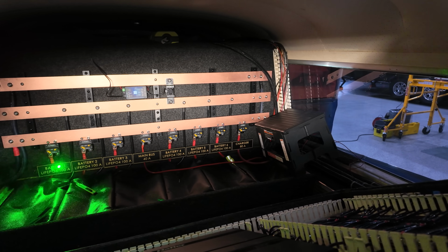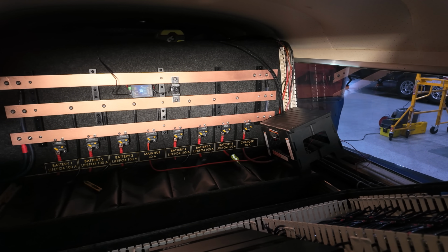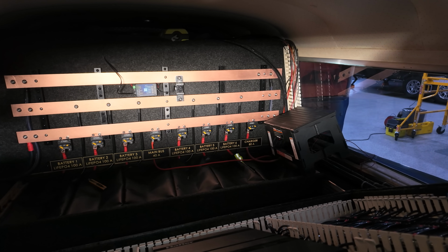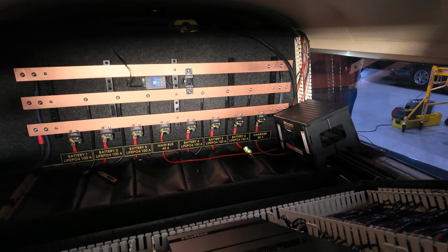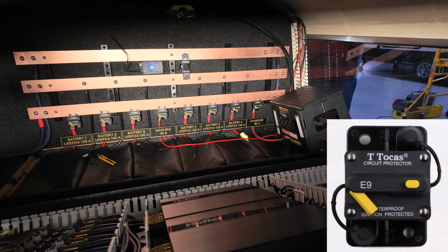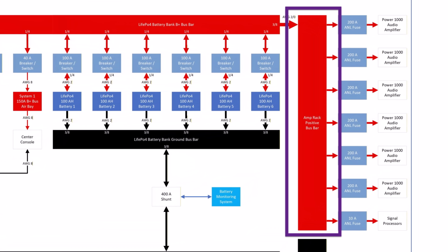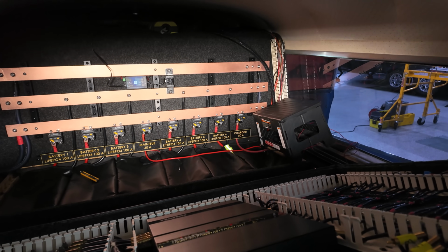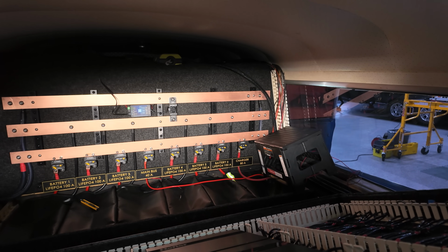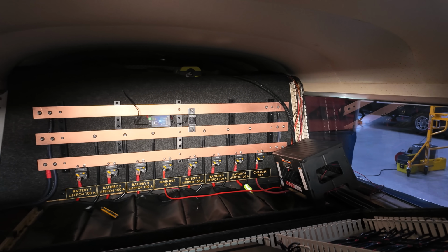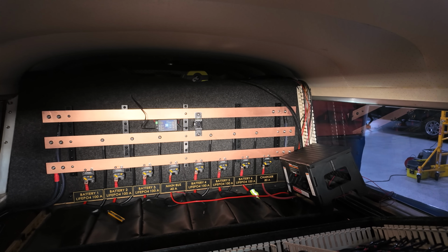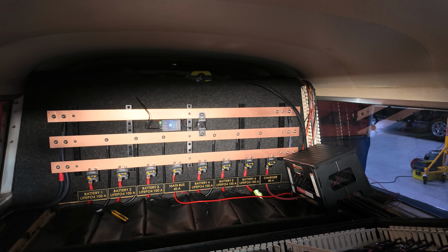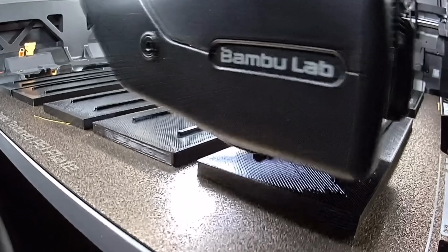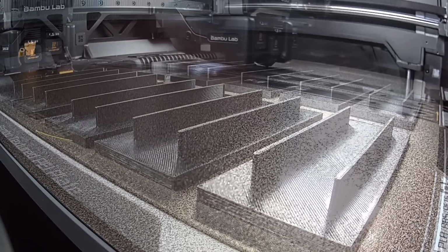I have 2-gauge AWG cable connected directly to a breaker, so it's only 20 inches long, and then these breakers are connected to this common bus bar. Breakers are really there in case of a catastrophic failure - like if the BMS system goes bad, that will prevent the cable from burning. Those are 100 amps, and I actually printed these placards on my 3D printer, which I love. I make all kinds of brackets and stuff with it.